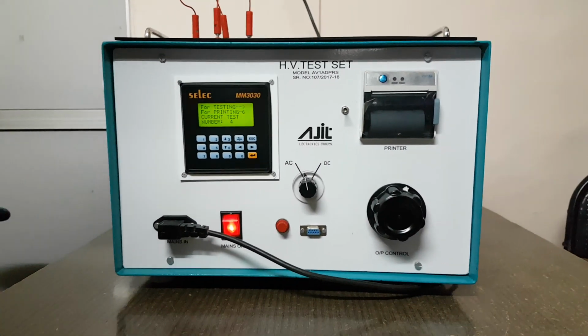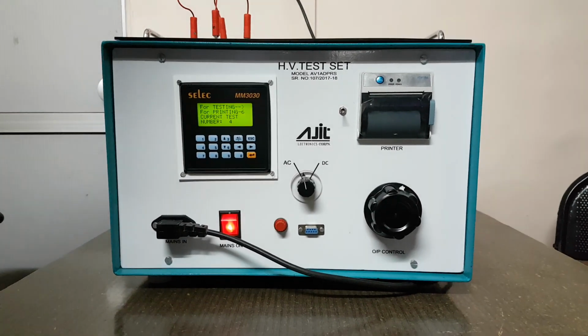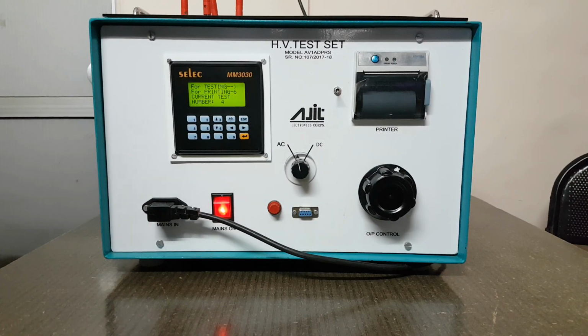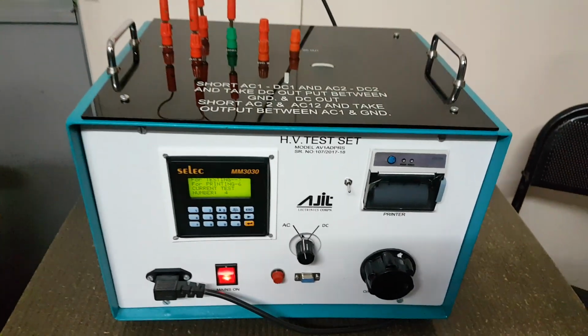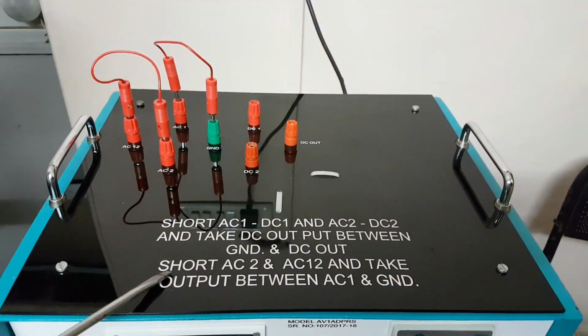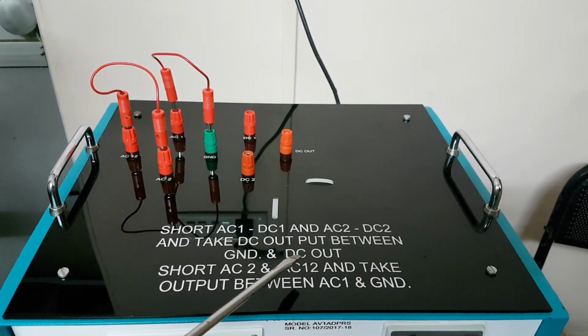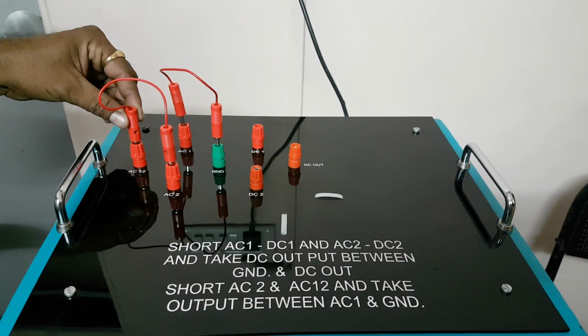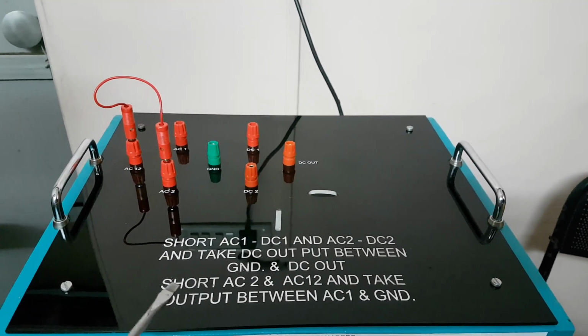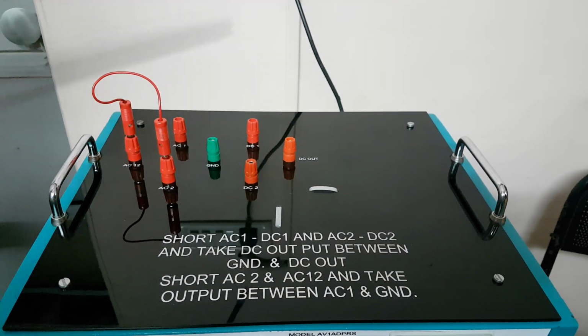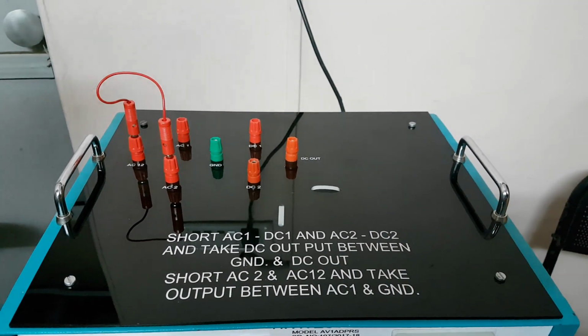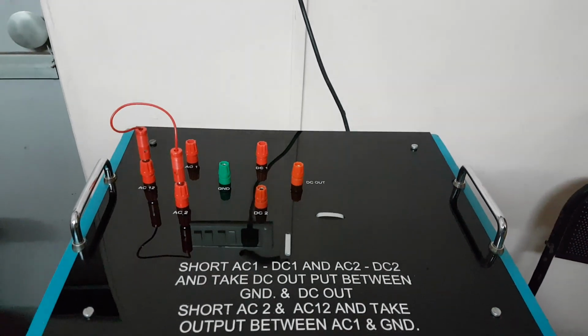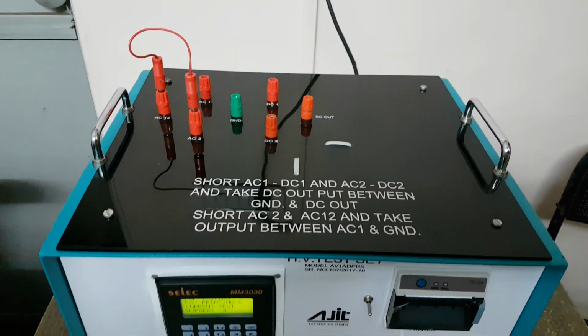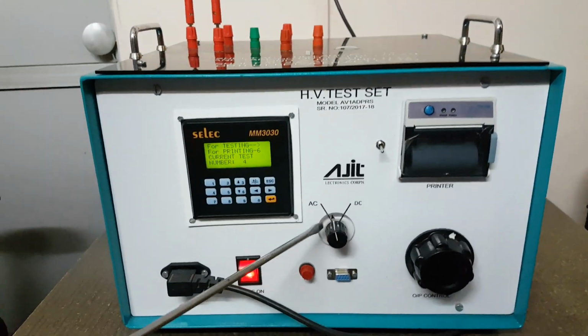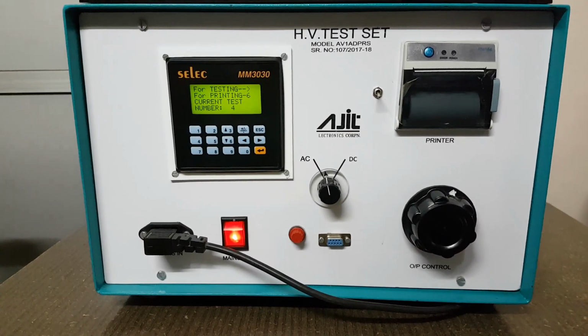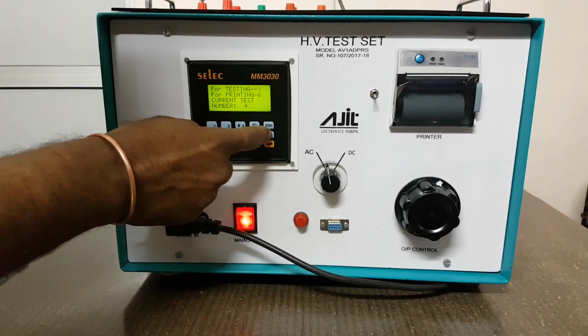Before that we have to configure the instrument for AC or DC. If we have selected AC output, then we have to configure the output terminals on the top panel accordingly. As per the instructions, for AC output we have to short AC2 to AC12 and take output between AC1, this terminal, and ground, this terminal. These are the AC output terminals. Now we have configured for AC, and the mode selector switch is also on AC, so the instrument will work for AC. Now let's go ahead with testing. Press arrow.